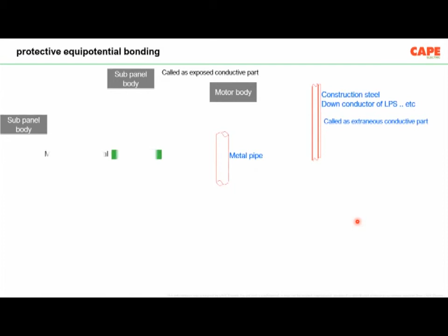In every building, the first step to protect any electronics is to have protective equipotential bonding. Of course it is implemented mainly for shock protection, protecting people from shock hazard, but it also has a role in protecting electronics, because the concept of functional earthing comes into the picture, and you have to integrate protective earthing and functional earthing in a building. If you don't have a protective earthing system in your building, forget about EMI, EMC.